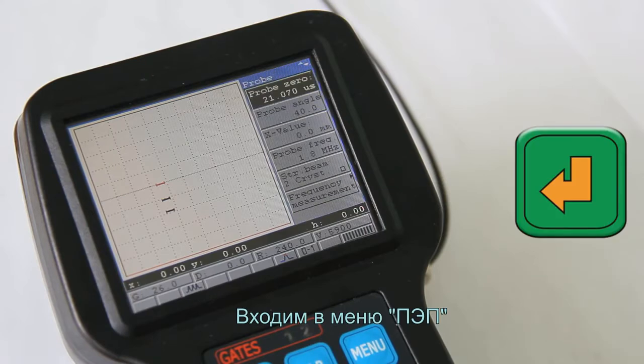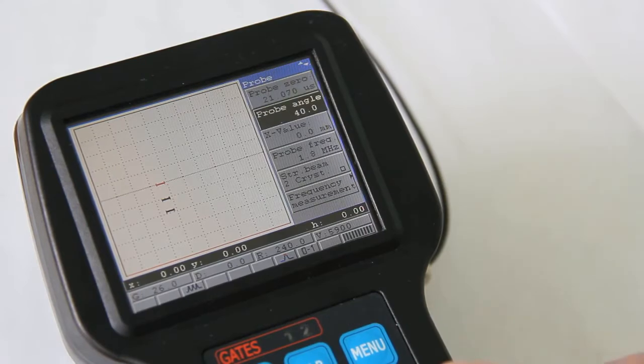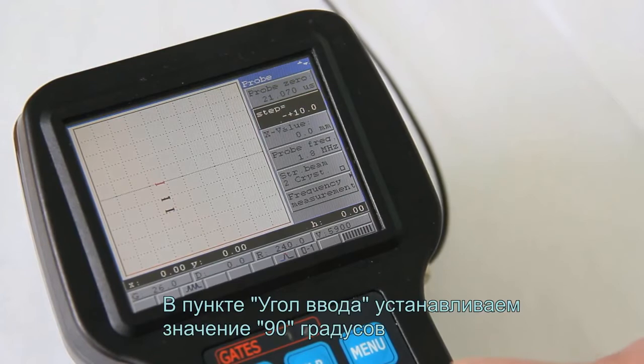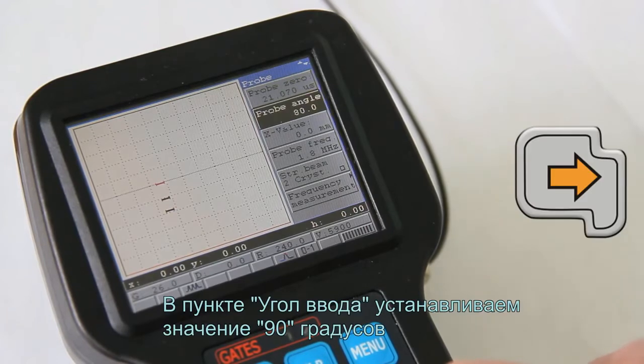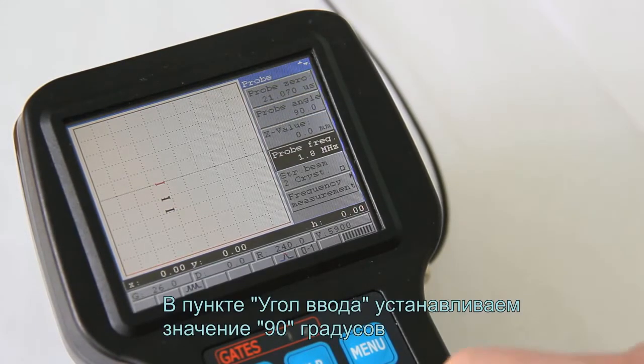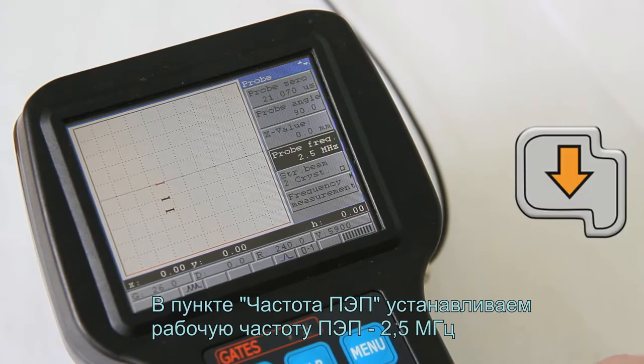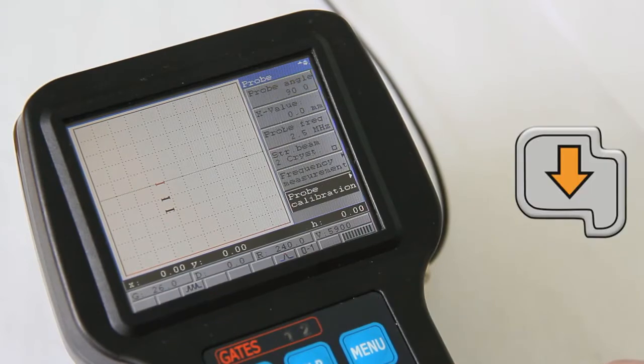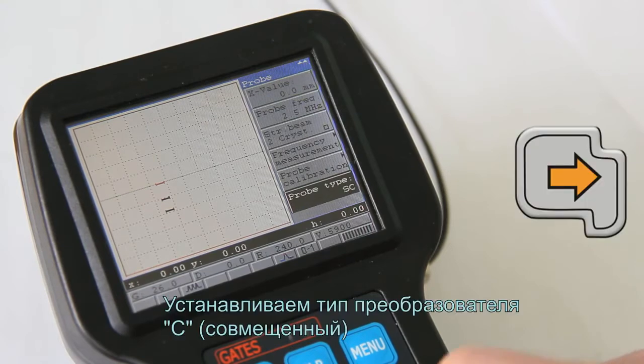Enter the probe menu. Set up the probe angle item to 90 degrees. In probe frequency item, set up the probe frequency to 2.5 MHz. Set up the probe type to SC, single crystal.